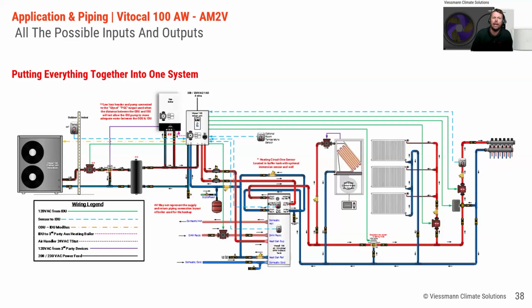And there's a couple of reasons why that is. One of the reasons is pipe sizing. Your system might only be piped off of that indoor unit in 1 inch, perhaps to your buffer tank it might be 1.25 inches. We should have 1.5 inch piping going from the indoor unit to the DHW tank for the flow rates that are necessary, given we're making domestic hot water at low temperatures. So although you could pipe your backup boiler to the buffer tank, and with all the pumps running, it theoretically would go back through the return and into the indoor unit and go to the DHW tank, in all theory, that would work.